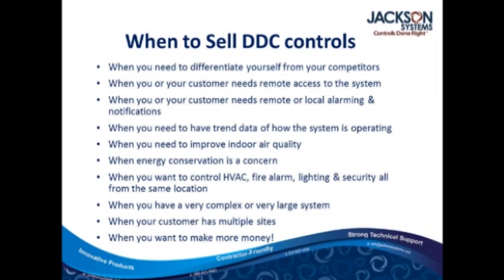When you need trend data to prove what you're doing, again, we'll pick on the schools. They hear a lot about sick building syndromes, but if we can monitor how much fresh air we're bringing into the building and document that amount of fresh air, when there is a problem, it makes it a little easier on the superintendent or whoever to say, hey, look, we have some sick kids, but we're bringing in the ASHRAE standard of 15 CFM per person, and we can show you how and when that happened.